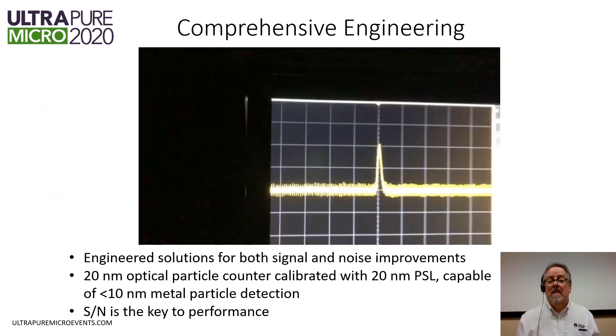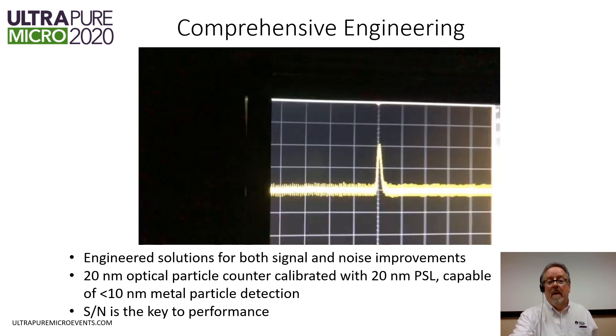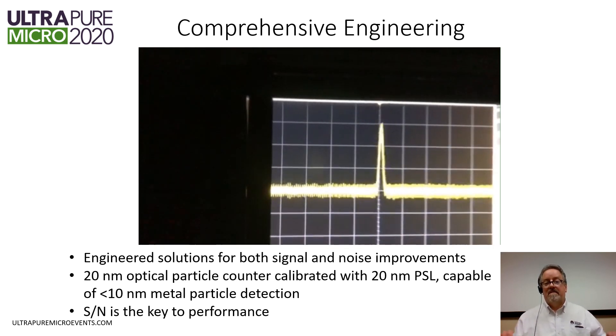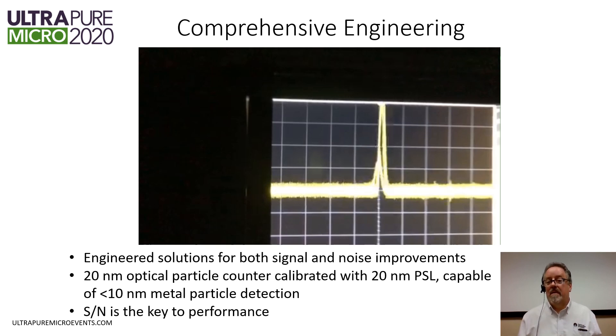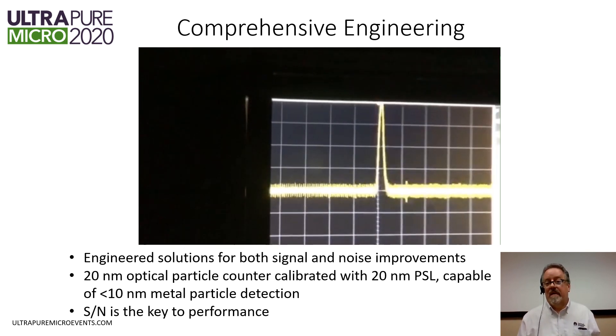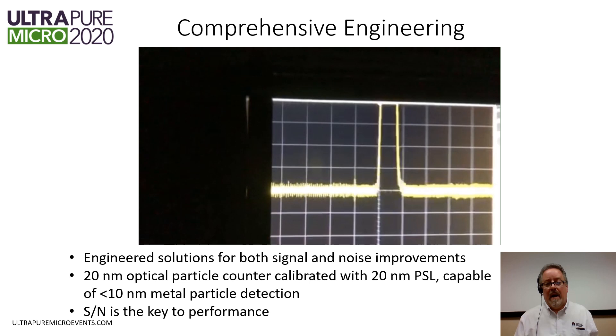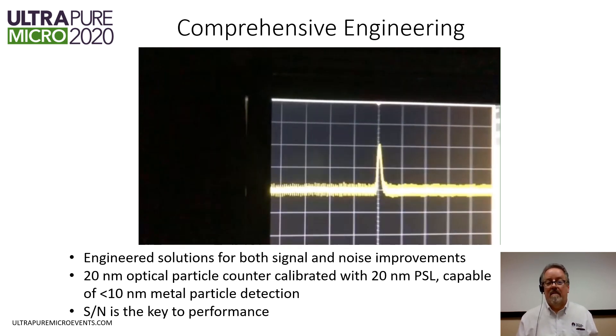This drives us to take comprehensive engineering improvements, finding solutions to both increase signal and reduce noise. Here is a video of 20 nanometer polystyrene latex spheres we use for calibrating our particle counters. As they pass through the particle counter, you can see the noise as the fuzziness of the line to the left and right of the particle signal — that defines how small we can see. We need to make sure our particles are well above that noise floor. In this case, at 20 nanometers, we're getting a lot of signal compared to our noise. Even though these are calibrated with 20 nanometer PSLs, this technology can see metallic particles smaller than 10 nanometers due to the difference in refractive index. Signal-to-noise is really the key performance metric.